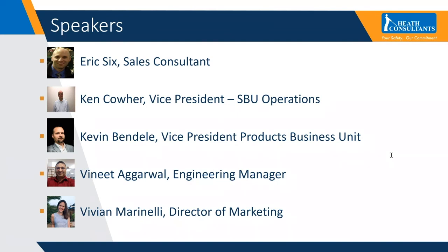Just a couple quick questions that came in. Can it be used to check LEL levels during venting? As Eric mentioned, it's essentially either a percentage gas mode or a ppm mode. LEL is a conversion factor: 500 ppm is 1% LEL, or 5%, or depending on your utility it may be 4% as the LEL level. So you can convert that reading into LEL yourself, but there is no display of LEL on the screen.